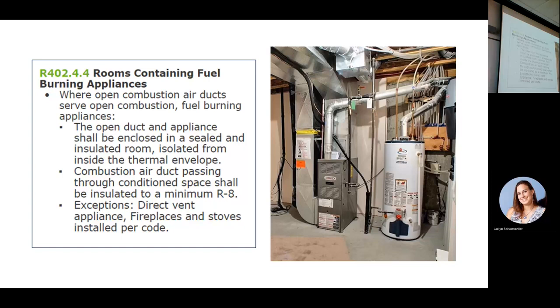The combustion air duct passing through the conditioned space shall be insulated to a minimum of R8. So we have to build a little room, we have to insulate it to the level of a basement, which would be R15. Has to be sealed all the way around, which is really tough, isn't it, to insulate, to seal around that whole duct system and everything. In fact, it's brutal to think about it. Weather strip door, tight. What's happened all of a sudden, we put the air handler, the furnace, outside the thermal envelope. Now we have to pressure test the duct system because our air handler is not inside the space. We have to insulate the duct because it's outside the space.